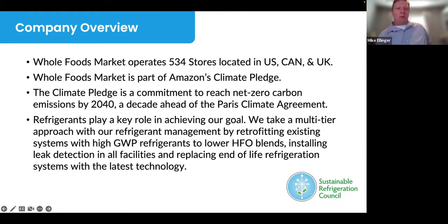Refrigerants obviously play a huge part of that, and we take a multi-tiered approach to addressing them. We actively retrofit high GWP refrigerants - we got through R22 a long time ago, so now we're focused on the 404s and 507s of the world, anything high GWP. Many of those go to lower HFO blends.